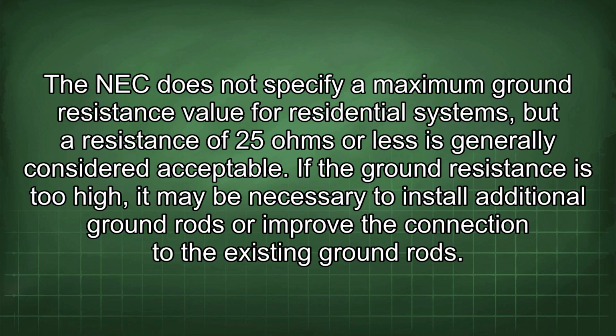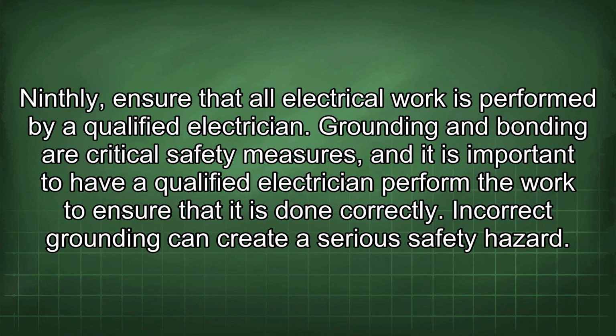If the ground resistance is too high, it may be necessary to install additional ground rods or improve the connection to the existing ground rods. Ninthly, ensure that all electrical work is performed by a qualified electrician. Grounding and bonding are critical safety measures, and it is important to have a qualified electrician perform the work to ensure that it is done correctly. Incorrect grounding can create a serious safety hazard.